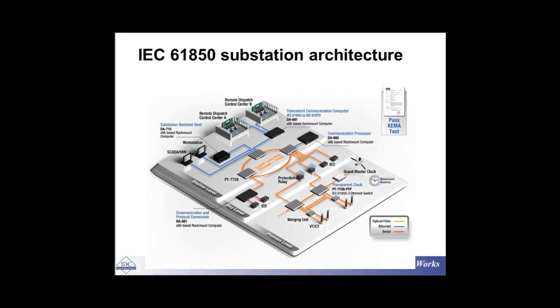But what has also been added in here is some kind of time synchronization. You can see that we have got a clock. It's a satellite clock. So it's very important that in terms of the timing of these signals, everything is perfect, so that all these stations and the receivers and the transmitters have got the same information and understanding about the time the signal was sent or the time the signal was received. So this time synchronization between all these levels is very important.